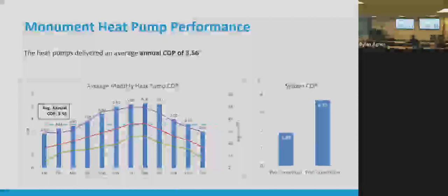This is just the monthly coefficient of performance, COP, of the heat pump. One thing I wanted to point out is that it was a very cold climate, a little colder than Boise, I think. Climate zone 5B, certainly a lot of days, a lot of hours in the teens and single digits. Even in the coldest winter months, December, January, February, we're hovering right around a COP of 3. Of course, when it's warmer and there's not much of a delta T, COP is high, in the 5s, but the annual COP is 3.5.